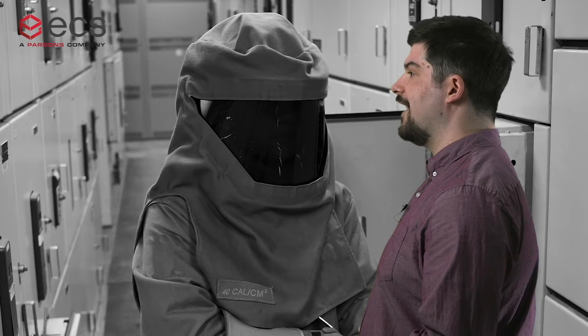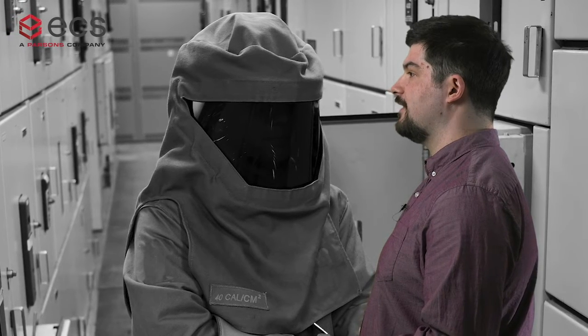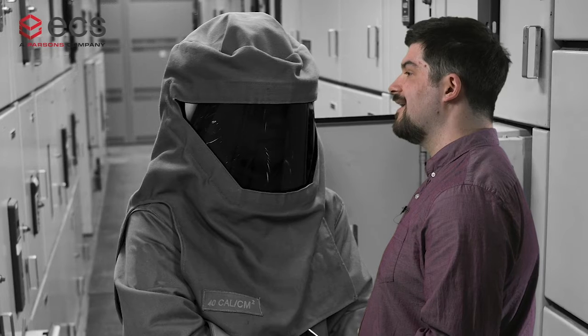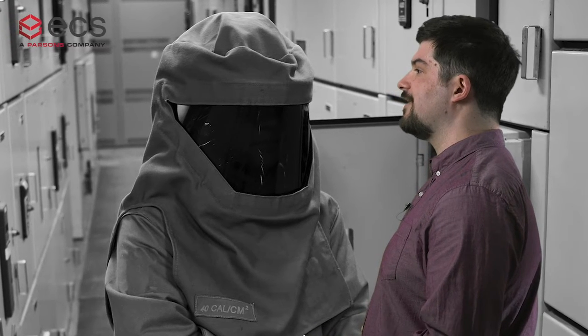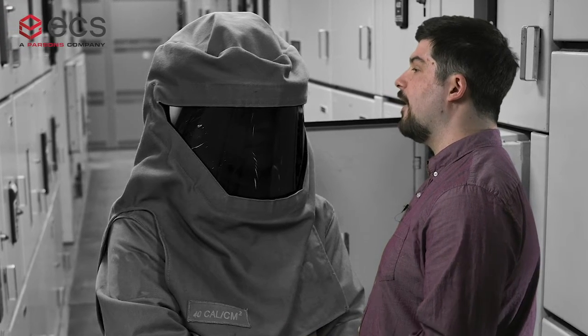Another critical part of our arc flash studies is determining the incident energy and protection boundaries at each piece of equipment. Then, we provide proper arc flash labeling to help keep your employees safe. This labeling states what personal protective equipment they must wear and where they are allowed to stand.